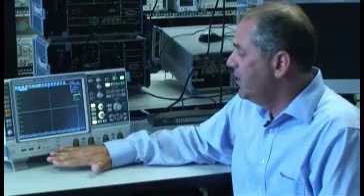Here we'll take a look at the noise level in the oscilloscope. At this point I have no signal connected to the oscilloscope input and I've got the input set to 50 ohm load.